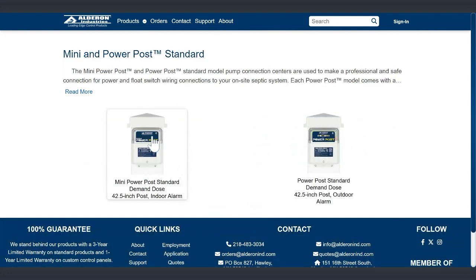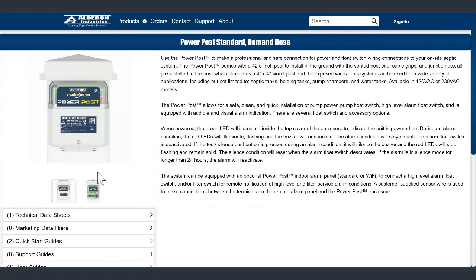simple. Our mini is basically just a junction box on a 5x5 PVC fence post, which lets you put that out by your septic tank, do all your wiring, and that's it. And then we have our standard here. This one has terminal blocks and power, zoom in a little more. So we have separate terminal blocks for incoming power and for your float, and an auxiliary output, so you can get audible and visual notifications right outside and or indoors.